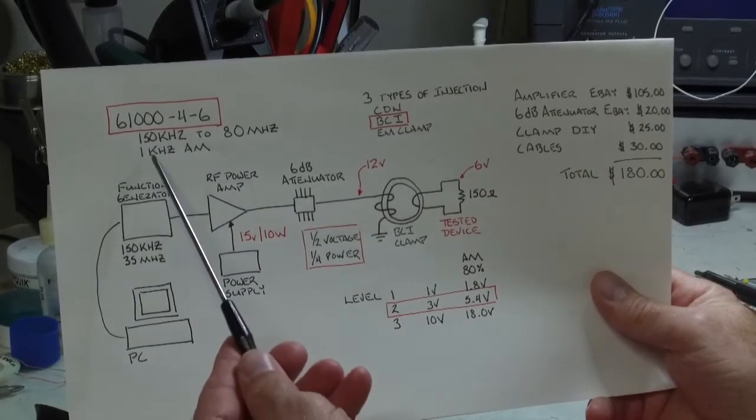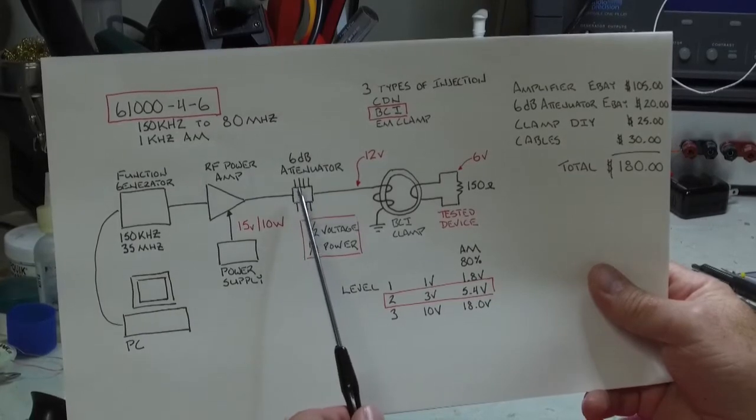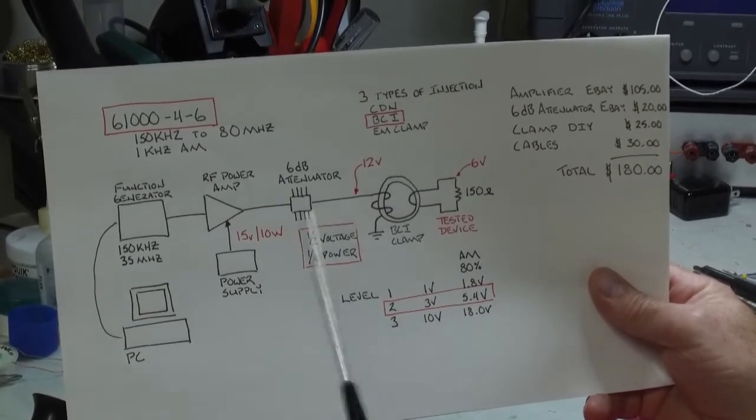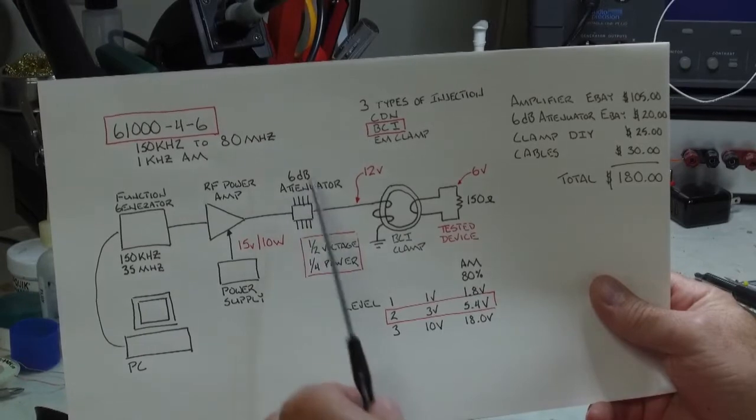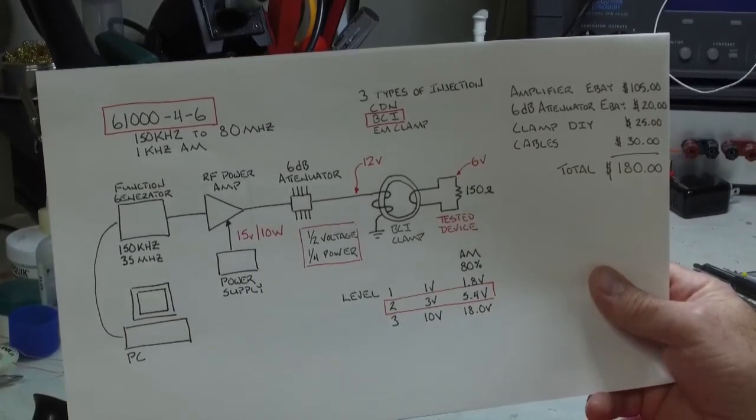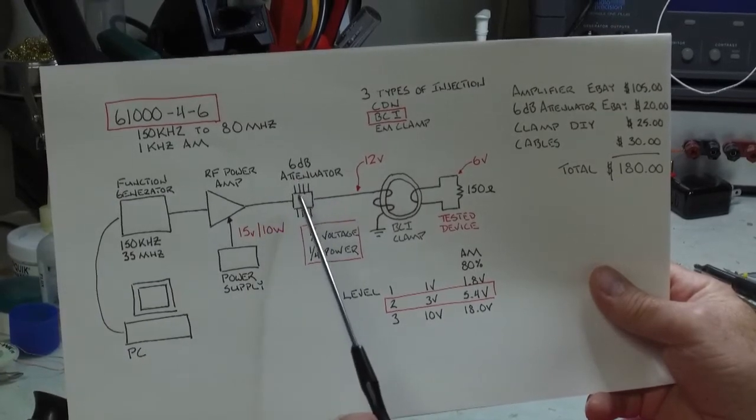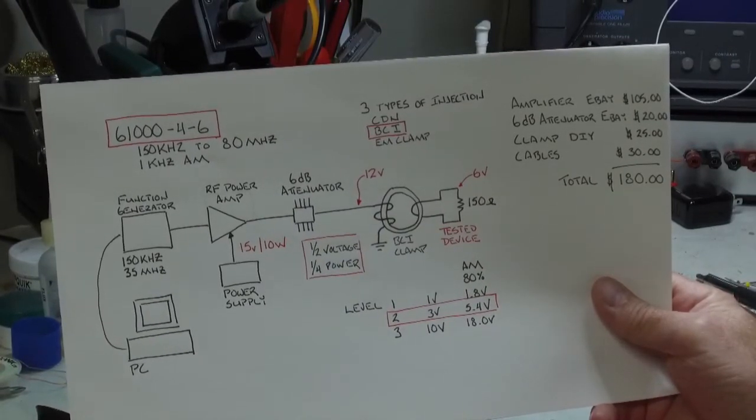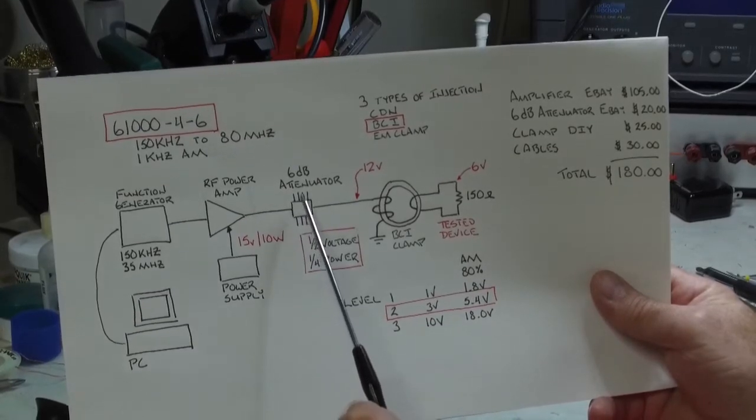It also needs to be able to modulate the signal at 1 kilohertz with AM modulation. There needs to be a power amplifier and then the specification notes that you must have a 6 dB attenuator in line before you drive your coupling clamp. This is a critical piece of the system and stabilizes the output of the power amplifier, presents a more stable impedance to the amplifier. However, it is a 6 dB attenuator so your voltage coming out of here going to your clamp will be half the voltage, or if you're thinking of power, your amplifier has to be 4x the power when this guy goes in circuit.